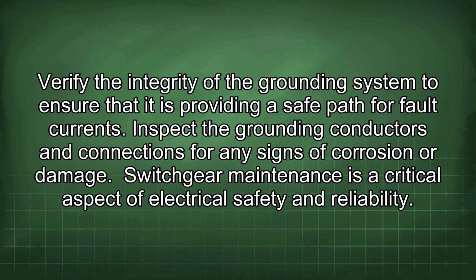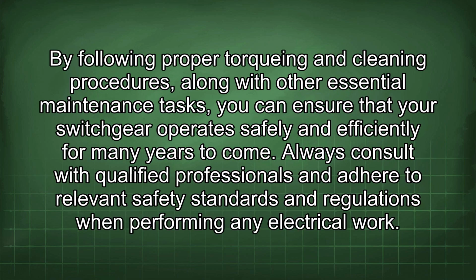Verify the integrity of the grounding system to ensure that it is providing a safe path for fault currents. Inspect the grounding conductors and connections for any signs of corrosion or damage. Switchgear maintenance is a critical aspect of electrical safety and reliability. By following proper torquing and cleaning procedures along with other essential maintenance tasks, you can ensure that your switchgear operates safely and efficiently for many years to come.